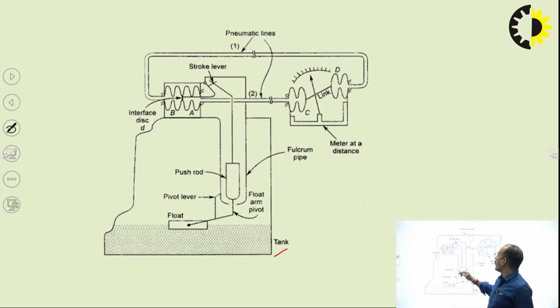By this stroke, A and B either expand or contract. In both cases, the pressure in this pneumatic line changes, and due to that change, the position of the C and D bellows also changes. That's why the point related to the scale connected to the C and D link shows the output on the calibrated scale. So here there is no use of electrical signal; you are just making mechanical arrangements. The level change is converted through displacement to the stroke, that stroke converts it to pressure, and that changing pressure shows on the pneumatic part.